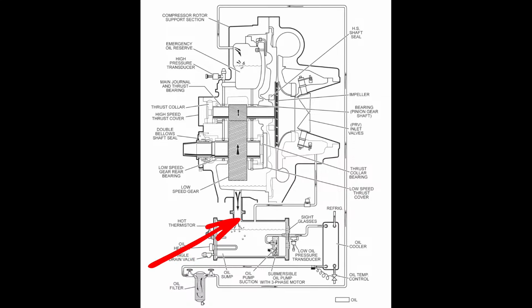Are you pulling amps while the machine is online? This heater should not be working while the machine is online. If I see amp draws while the compressor is running, I know I've got an issue, and I need to figure out, okay, more than likely that K1 relay has failed. Now, typically they fail open in my experience. They don't usually fail closed, but at any point, it could have an issue. Is that temp sensor in a dry well? I don't remember.